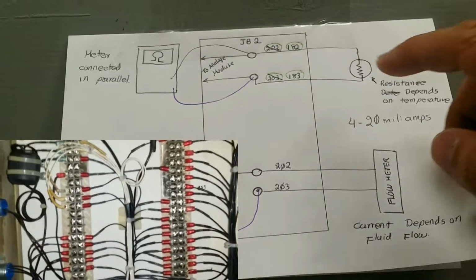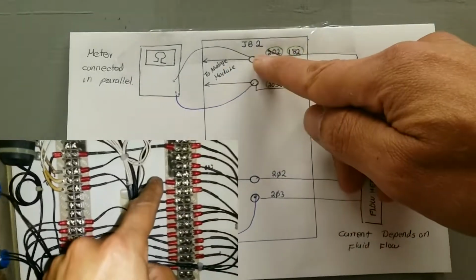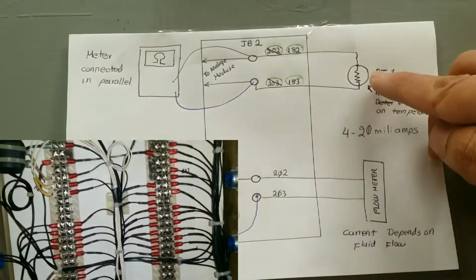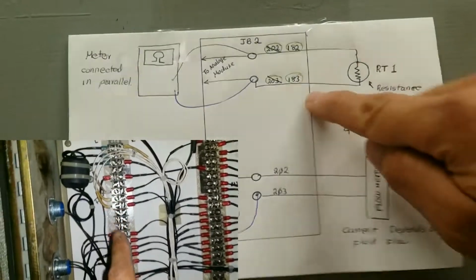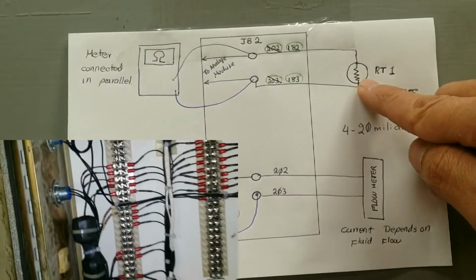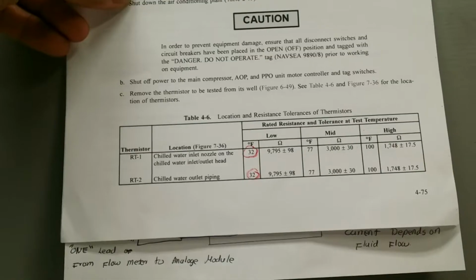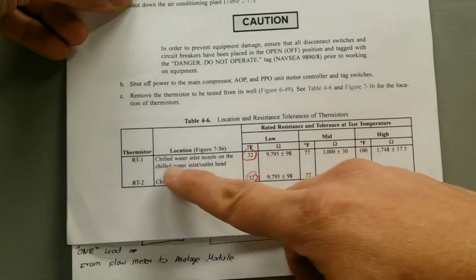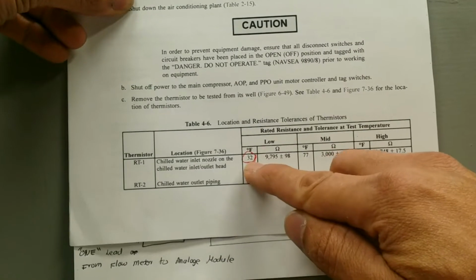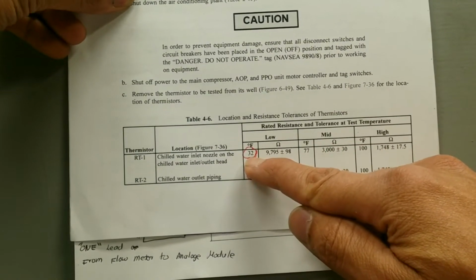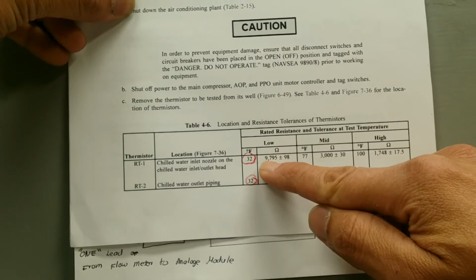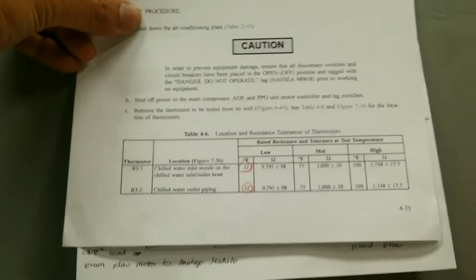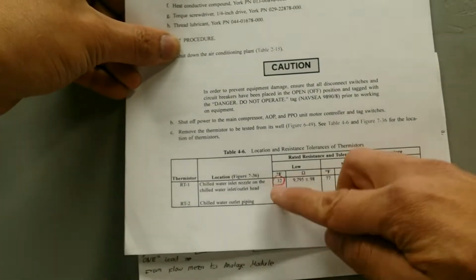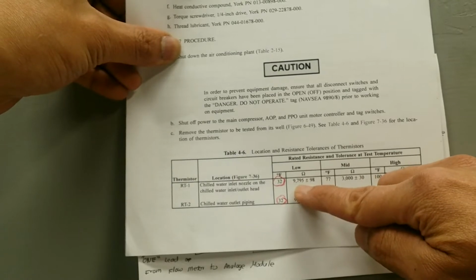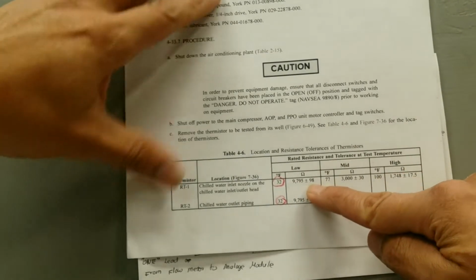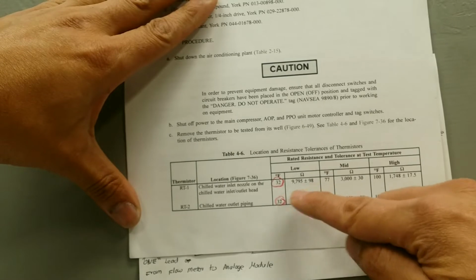So as a demonstration, here at RT1, you can put your multimeter in ohms, and based on the temperature that this one is, you can know if the sensor is reading right or wrong. Your tech manual will have a chart like this, okay? At 32 degrees Fahrenheit, it's supposed to have a resistance of 9,795 ohms, plus or minus 98, and it keeps changing as the temperature changes.